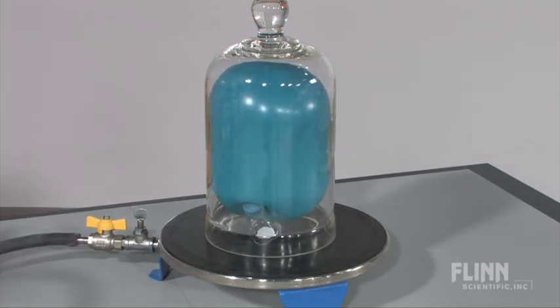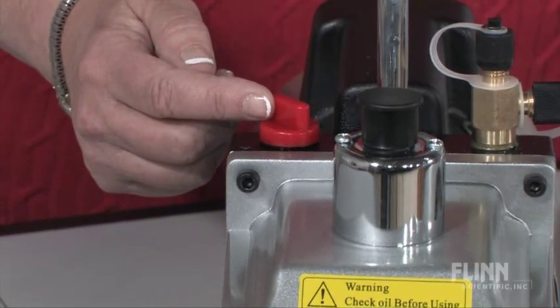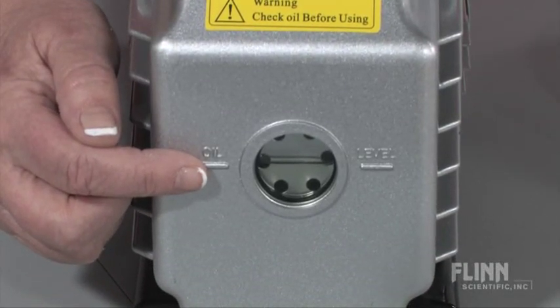can be achieved with a single-stage pump. The pump comes with vacuum pump oil that is easy to add through the oil port, and has an oil gauge window to allow for a quick check of the oil level.